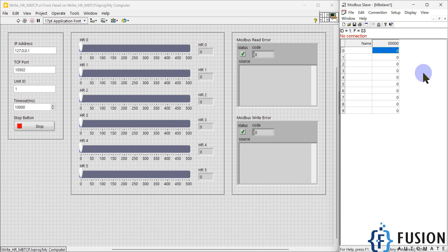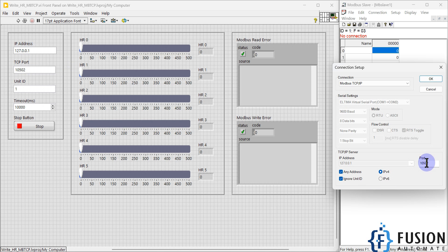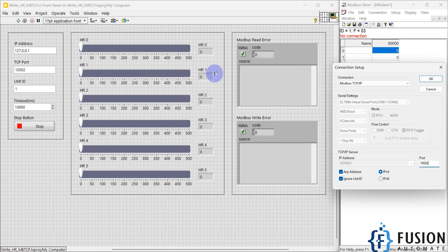The slave ID is 1. I'll press OK, then go to Connection and press Connect. The connection type is Modbus TCP/IP. The IP address is my localhost 127.0.0.1 — if you have a physical device, use that device's IP address. The port in the simulator is 10502, the unit ID is 1, and the timeout is 10,000 milliseconds. The number of registers and starting address are configured as constants in the back-end programming.